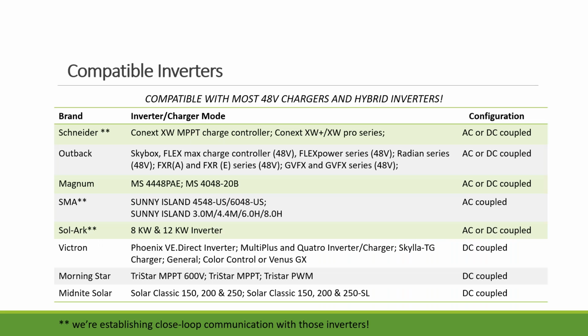Before we start to design systems step by step, here's a list of inverters that we are compatible with. The battery is designed so that you can work with different inverters as long as they require 48 volts DC input. You can use communication, or you can skip the communication if you parallel eVolt or, in the future, eFlex. We are working with Schneider, SMA, and others on the communication. The other batteries we currently do not communicate with, but again, you can just use the parameter settings in the inverters, and that will work fine too.